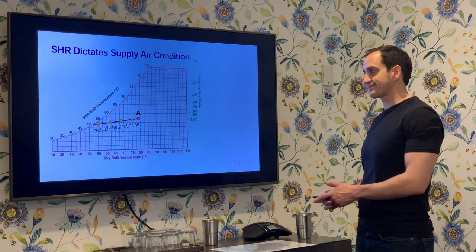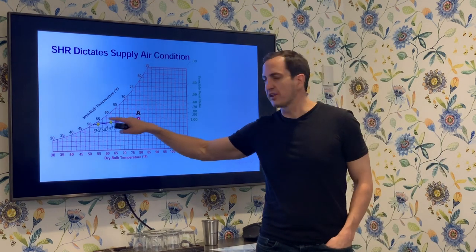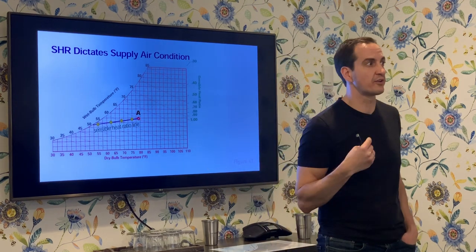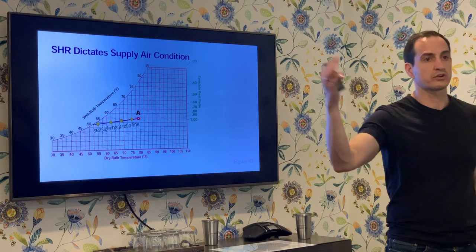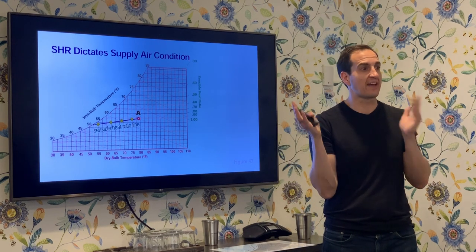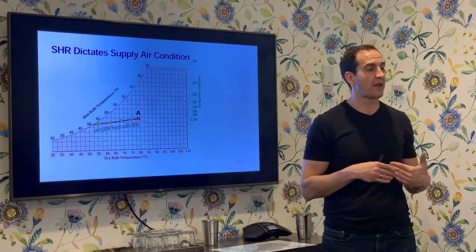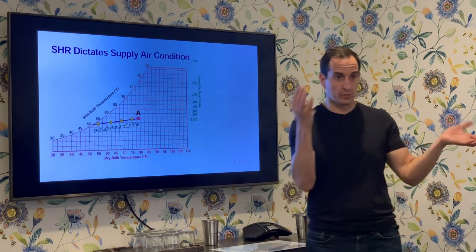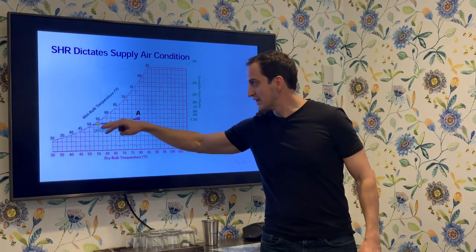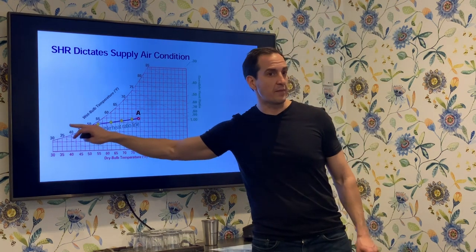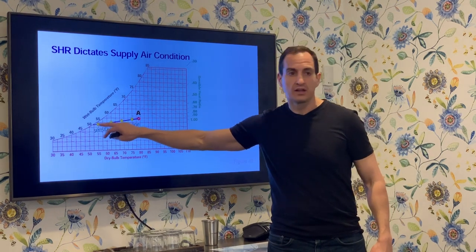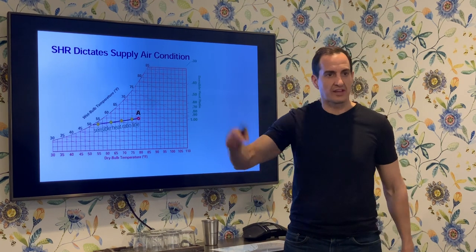If I know how many lights are in the room and how much water is coming out of the plants, I can calculate what sensible heat ratio I need to adequately keep the space at the right temperature. I take the point I'm trying to maintain and draw a line at that ratio away from it. The further I get from the room condition along that line, the less air I need to process per unit time to maintain the condition.